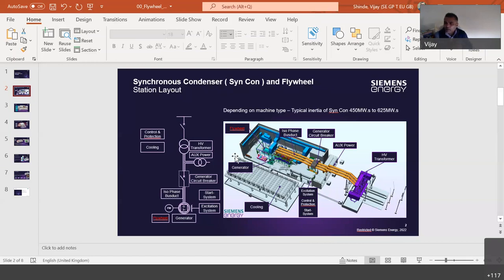In terms of megawatt seconds, we're talking about somewhere between 450 megawatt seconds to 625 megawatt seconds for a normal design of these machines, which is quite a large number. And you see there's a schematic on my screen which shows how the synchronous machine is connected to the grid and how it differs from the normal synchronous machine operation.